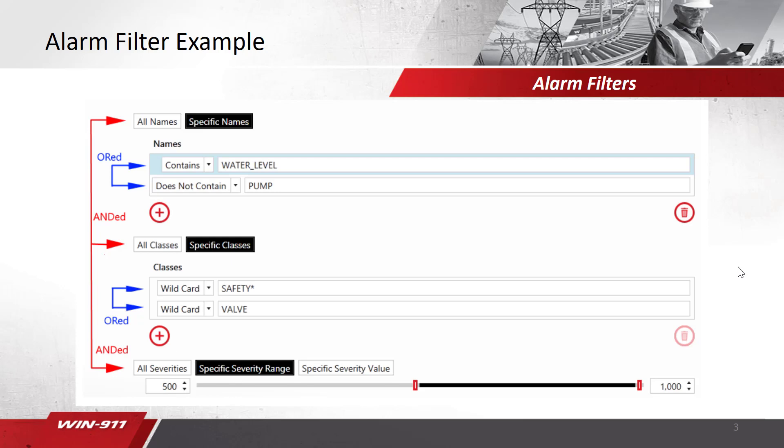So in this example, we are looking for something that contains the name water level, but does not contain pump. And so on down the list with classes, we are looking for something with safety, with the asterisk wildcard for anything after that, or the word valve. Finally, we are also looking for something that includes a severity range between 500 to 1,000. You can also filter on a specific severity value. For example, if you knew that the severity of the tag was 802, you could put just 802 by using a specific severity value.